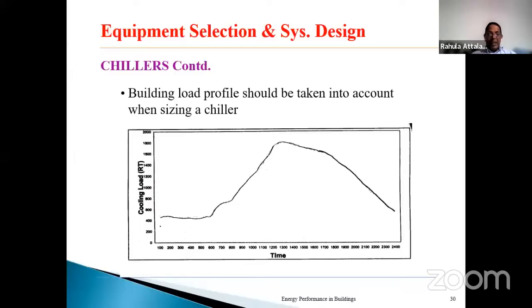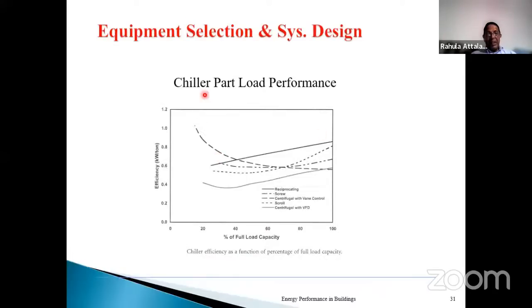And this is a diagram that indicates part load performance. Here it's the efficiency in kilowatt per ton as a function of the percentage of load. You see different chillers: reciprocating chiller, screw chiller, centrifugal chiller. The lower the number, the better the energy performance. Except here, where the lowest is about 45% for the centrifugal chiller, screw chillers and small chillers have the lowest kilowatt per ton at 60 to 70%. Therefore, 100% load efficiencies are not that much better than the 70% efficiency. So by slightly oversizing, you can operate in this region. That's where equipment selection is important.